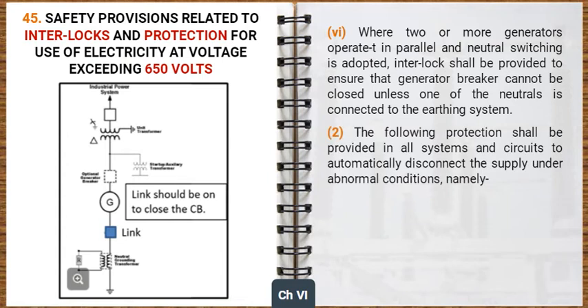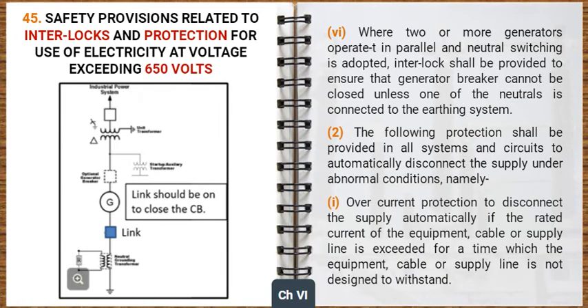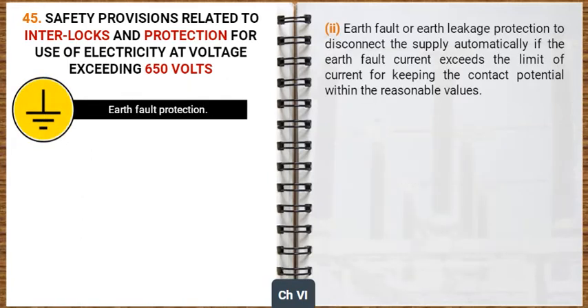The following protection shall be provided in all systems and circuits to automatically disconnect the supply under abnormal conditions, namely, overcurrent protection to disconnect the supply automatically if the rated current of the equipment, cable or supply line is exceeded for a time which the equipment, cable or supply line is not designed to withstand. Earth fault or earth leakage protection to disconnect the supply automatically if the earth fault current exceeds the limit of current for keeping the contact potential within the reasonable values.